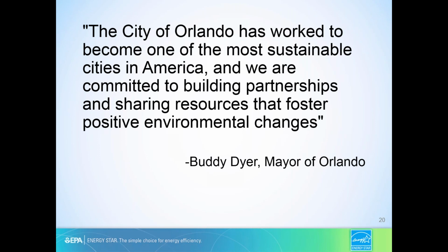One of the ones we recently finished and I'm most proud of is the Amway Center—I'm looking at it right across the street right now. We recently did an LED lighting retrofit. I don't think anybody else has entered a stadium into the competition, so it might not apply to everybody, but we went through the building and did an ASHRAE Level 2 audit, using the same methodology we're talking about here to find where we could get the most bang for the buck payback. Even though this is a fairly new building built in 2010, we identified the lighting system as a very large source of energy consumption. It's used over 200 events a year, both the sports lighting in the catwalk and the non-sports lighting along the concourses, concession areas, and back and front of house spaces, which uses a substantial amount of energy.